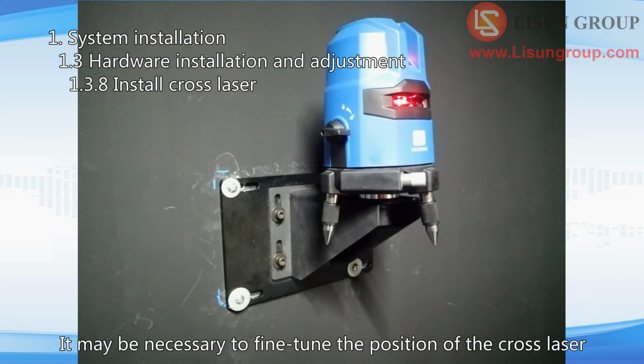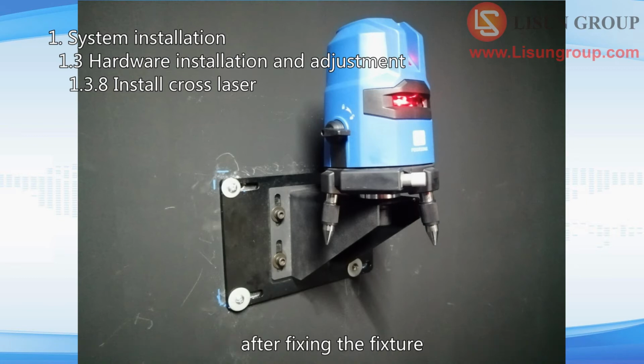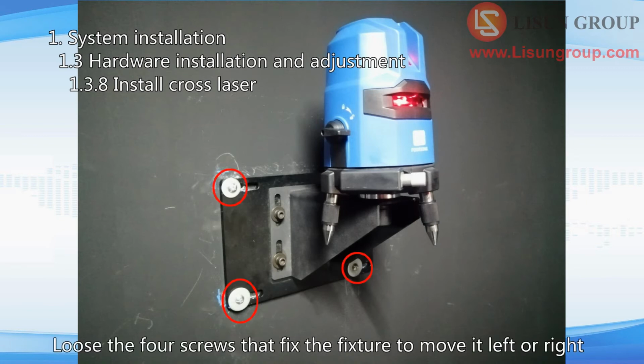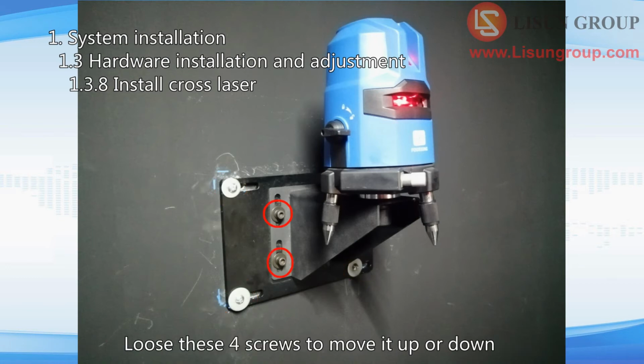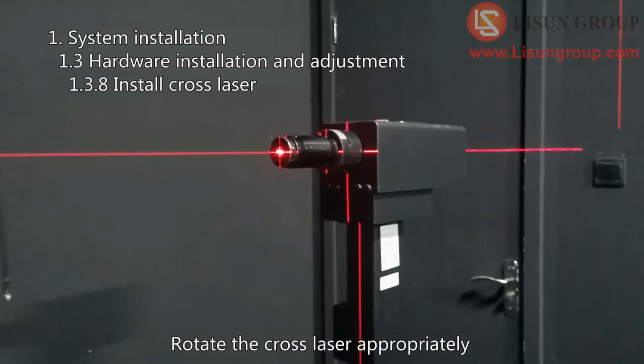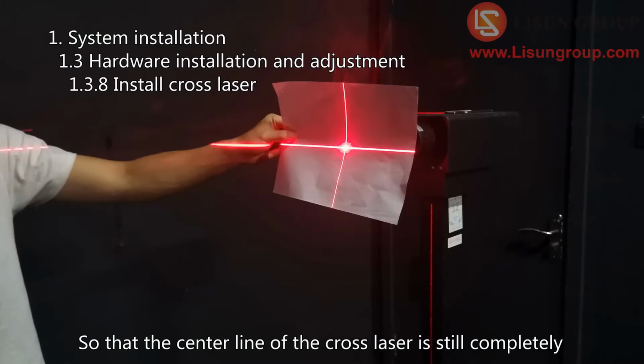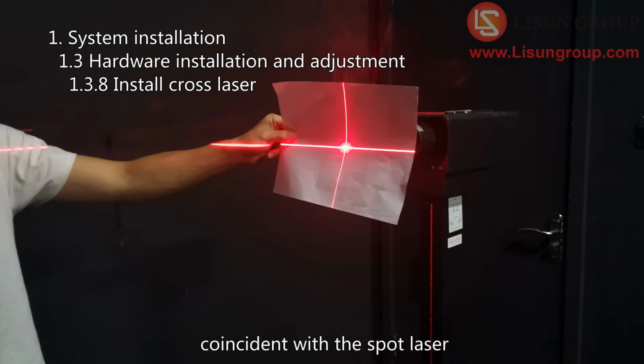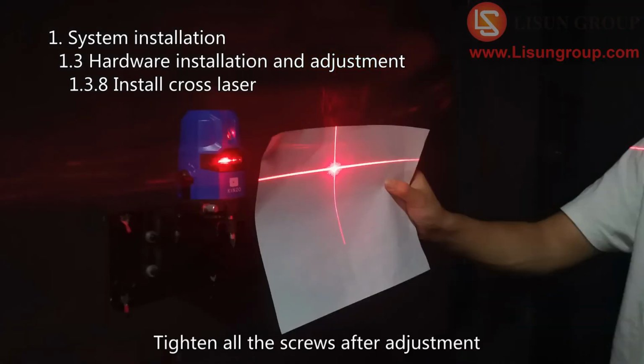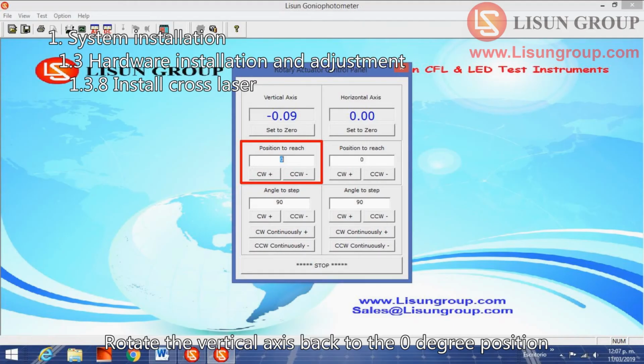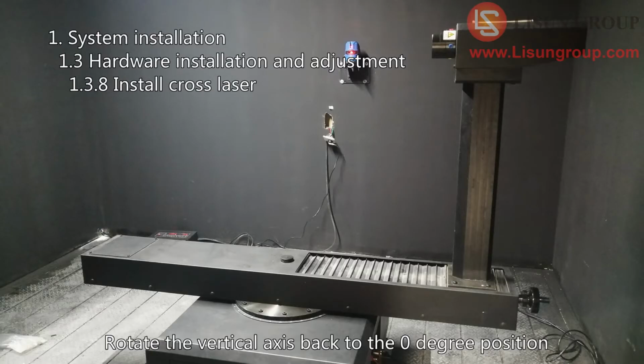It may be necessary to fine-tune the position of the cross laser after fixing the fixture. Loosen the 4 screws that fix the fixture to move it left or right. Loosen these 4 screws to move it up or down. Rotate the cross laser appropriately so that the center line of the cross laser is still completely coincident with the spot laser. Tighten all the screws after adjustment. Rotate the vertical axis back to the 0 degree position.